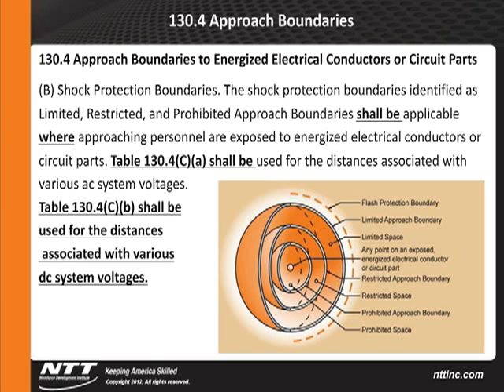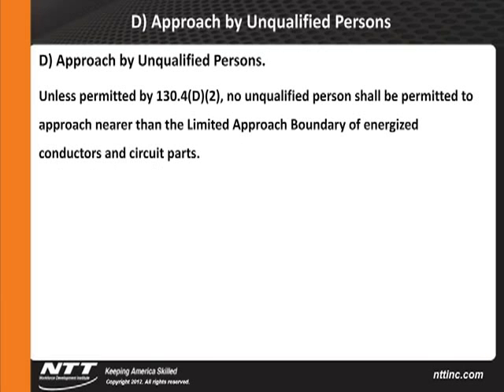What about approach by unqualified persons? Unless permitted by 130.4(D)(2), no unqualified person shall be permitted to approach nearer than the limited approach boundary of energized conductors and circuit parts. 130.4(D)(2) deals with exposed overhead movable conductors. So again, more requirements to keep unqualified people out of that work zone.